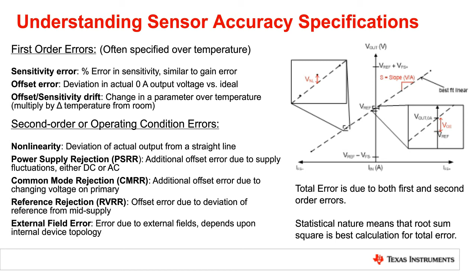The combination of all those, as well as errors from external fields and from other things, give you a total error curve that is really what a customer ultimately cares about, because that's how the sensor is going to perform in the system. When we look at total error calculations for the TMCS1100, I've shown the datasheet specs here for all those errors that we just referenced. Typically, we like to look at this as total error versus input current, because it's not just the full scale or maximum current error that you care about.